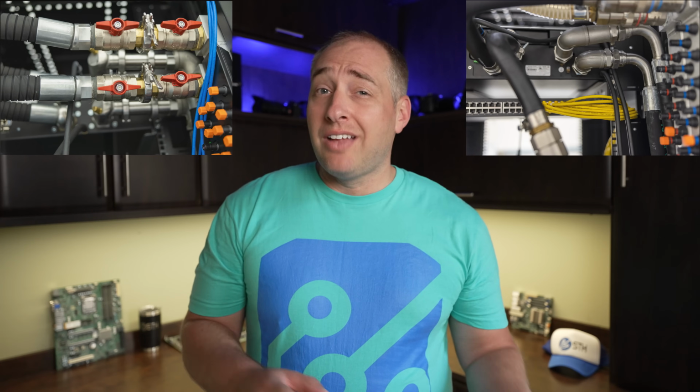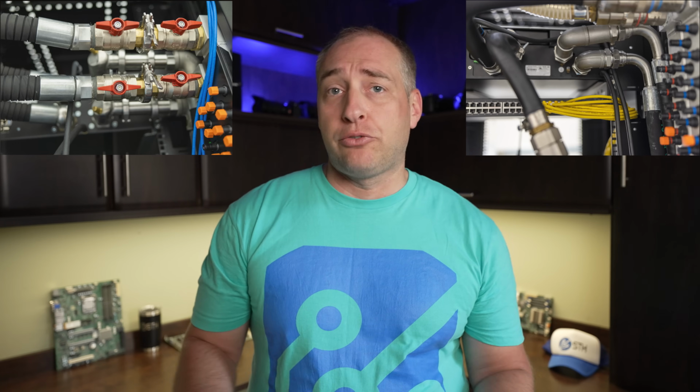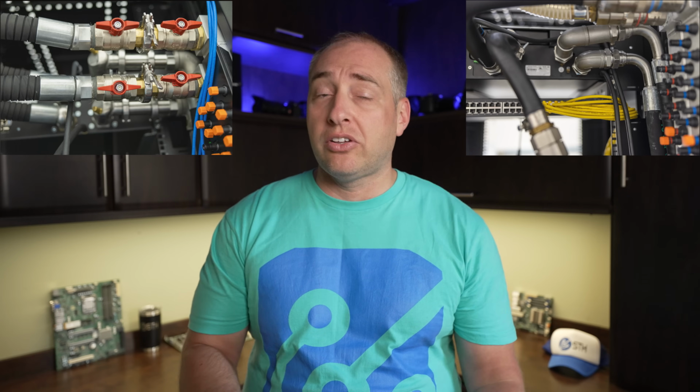And the reason for that is actually kind of easy. It's just the fact that the liquid is taking that heat away from those chips in a more efficient manner than if you're trying to blow fans over just copper or whatever heat sinks. Now, what's not included in that power consumption figure is the water pumps and any of that kind of infrastructure. So there's definitely power usage happening outside of the actual server that we're not including here. But just at the server level, it was only about 200 watts more, even though you would think it might be 800 watts or more because you'd spin your fans faster.